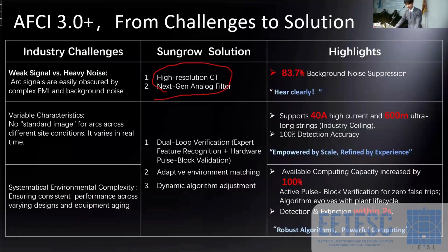I want to emphasize here that dynamic algorithm adjustment calls for the 3-level detection. We also introduce the deep learning method. Basically, every plant will have its own characteristics, so the algorithm will adjust the threshold of the arc fault to make it more accurate. So that's the dynamic algorithm adjustment. And that's the last area, a highlight.